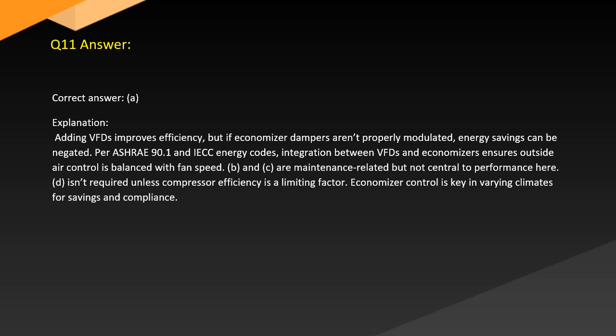Correct answer: A. Adding VFDs improves efficiency, but if economizer dampers aren't properly modulated, energy savings can be negated. Per ASHRAE 90.1 and IECC energy codes, integration between VFDs and economizers ensures outside air control is balanced with fan speed.